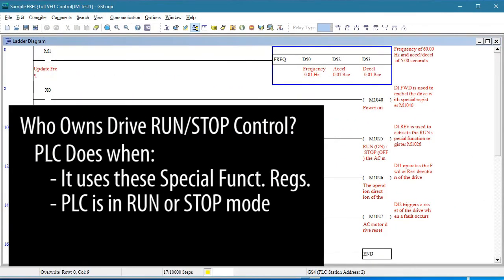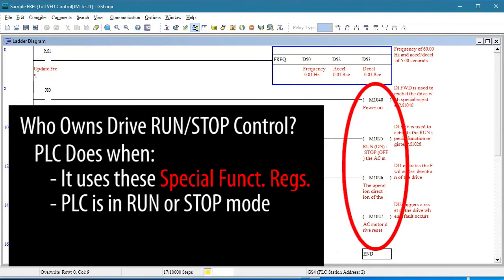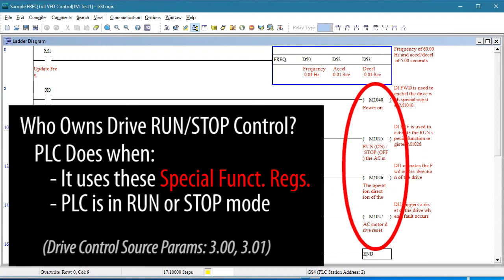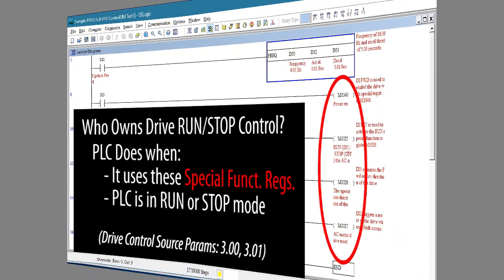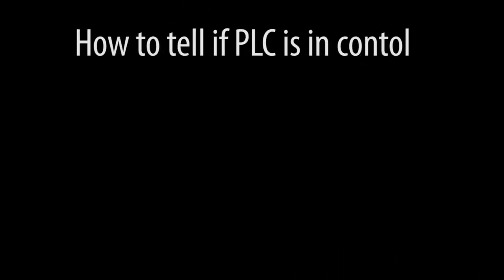Likewise, if you use any of these special function registers to control the drive, even just one of them, the PLC owns run, stop, forward and reverse of the drive as long as the PLC is enabled. If the PLC is disabled, then parameters 3.0 and 3.1 regain control of the drive until the PLC is enabled again.